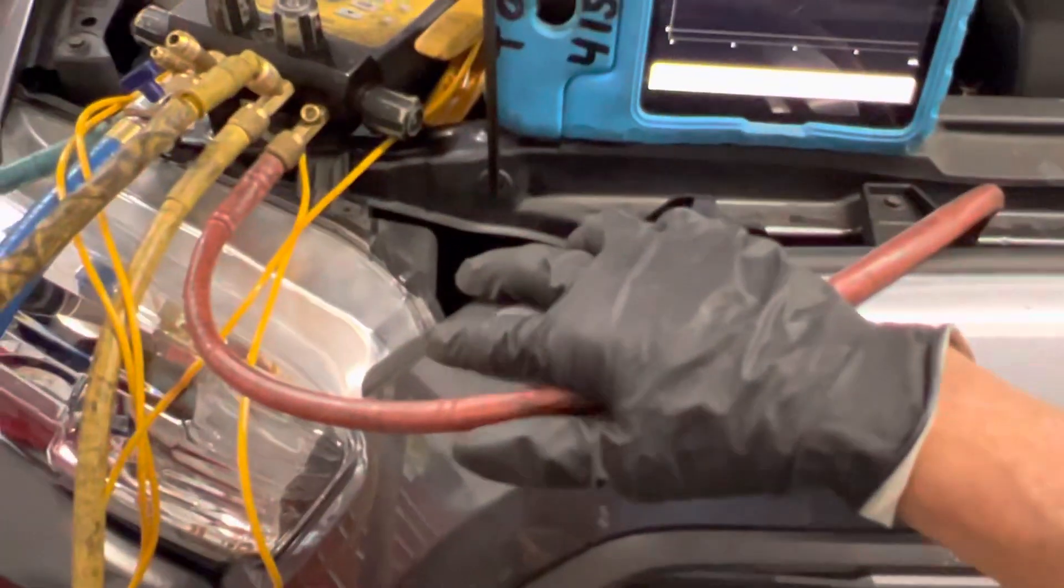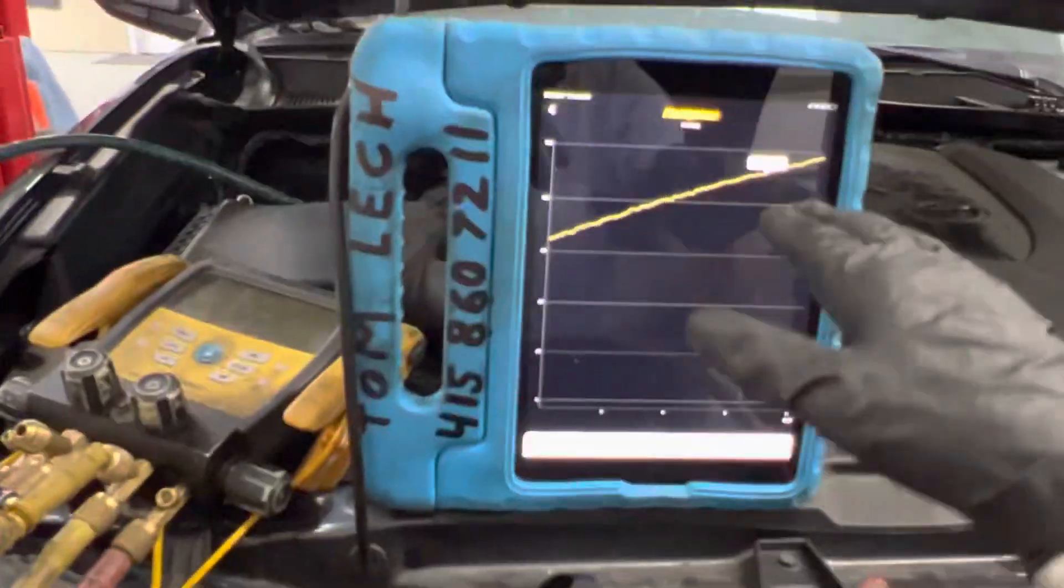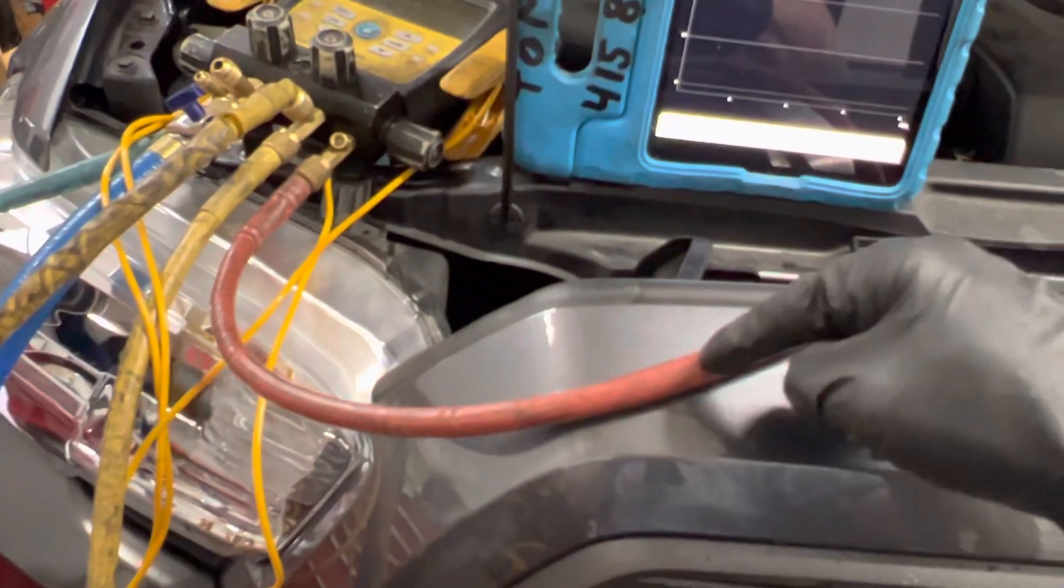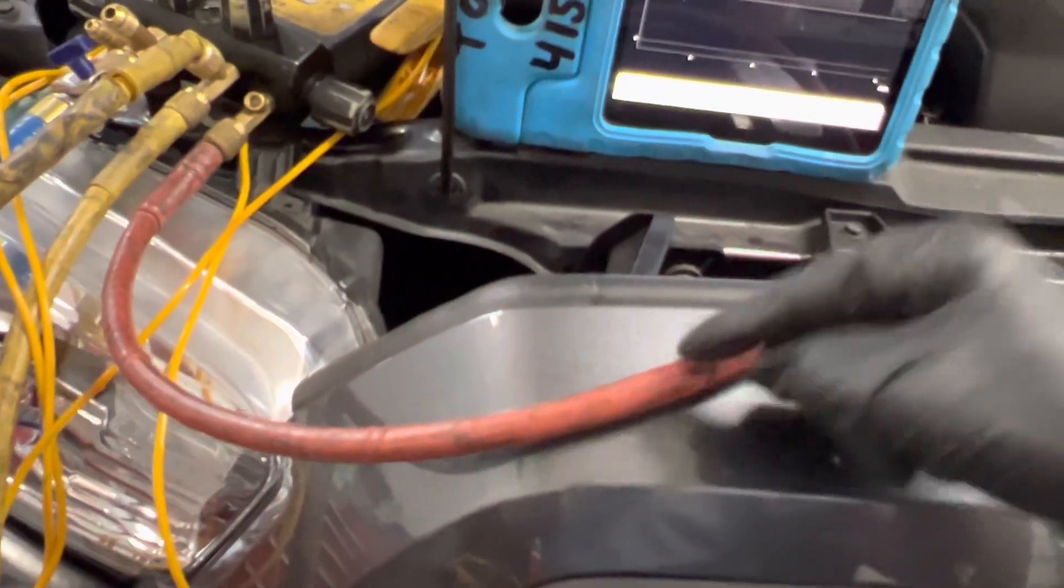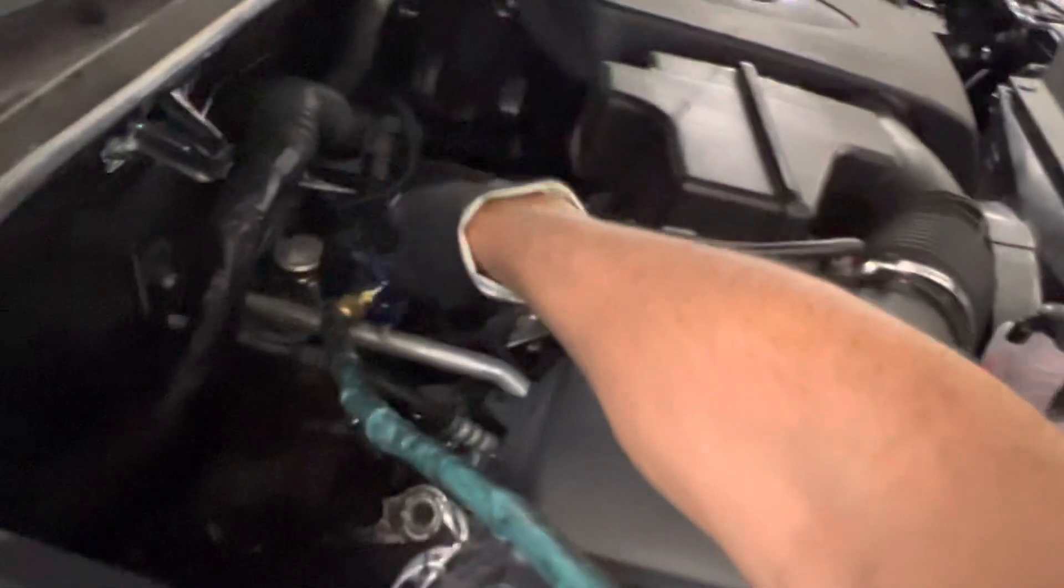Using refrigerant gauges, especially on an overnight recovery, your decay might go up 500-700 microns just because you used these rubber refrigerant recharge hoses and gauges.